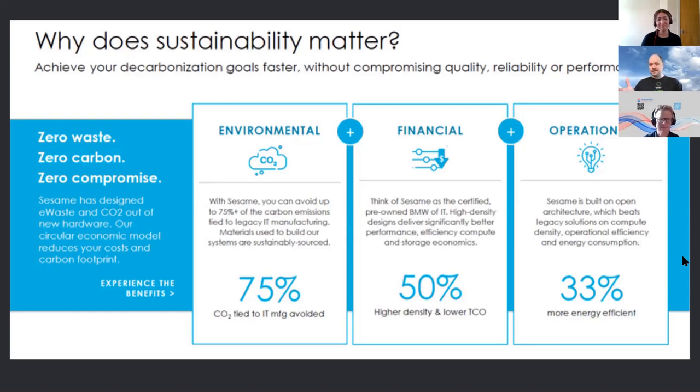And then finally, with some of the leverage, including the technology from Asperitas, we're able to reduce the day-to-day operational costs, right? The total amount of energy, the energy that isn't being used to move the fans, the natural convection inside the tanks, rather than mechanically using electrons to move air or fluid. And the increased density, right?